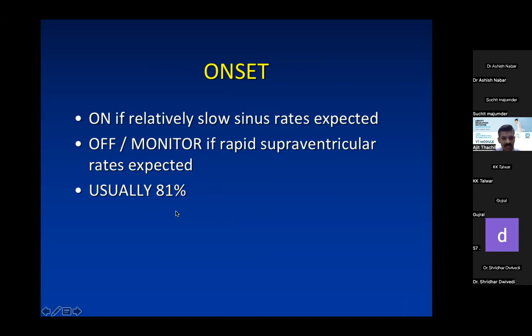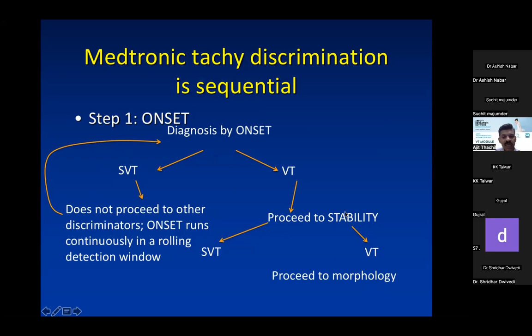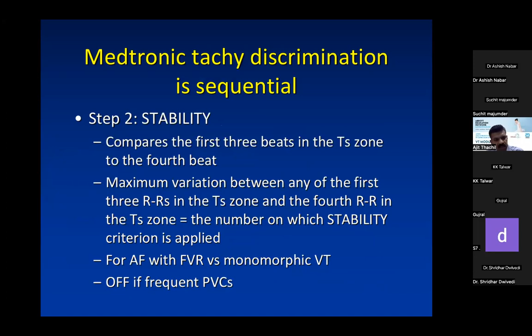Now, the other thing which you need to understand only with Medtronic is that Medtronic discrimination is sequential. For example, if onset says SVT, it will not look at stability or morphology. If stability says SVT, it will not look at morphology. But if onset says VT, it will look at stability. If stability says VT, it will go to morphology, which means that if you put all 3 on, but onset says SVT, the other 2 are as good as being off. Stability compares the RR variability between beats. I will not go into how it is.